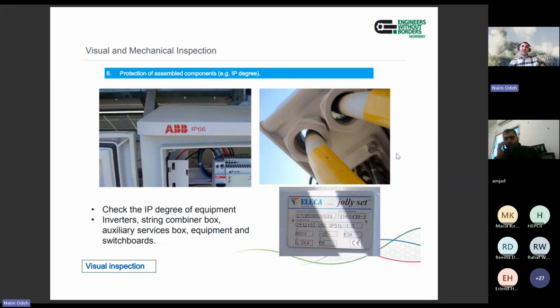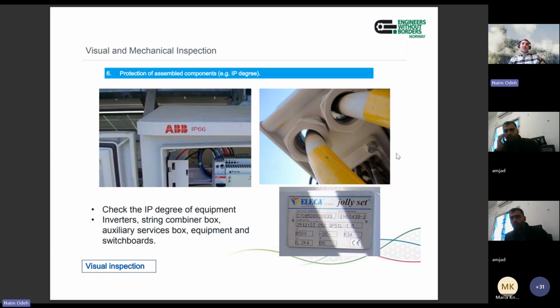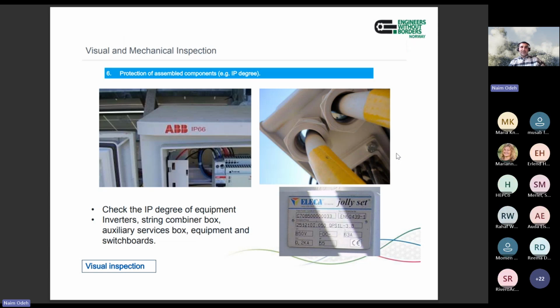So IP rating should be maintained. When you purchase equipment or an enclosure with an IP rating, the IP rating was selected based on the location of the installation of this box. It is not a random number. This is critical and it has a meaning. So it is very important to maintain this IP rating. And to do so, all manufacturer recommendations in this regard should be followed. There are recommendations and procedures for each of these activities that are expected to happen in such enclosures, where you need to have openings for cables, in and out, and so on.